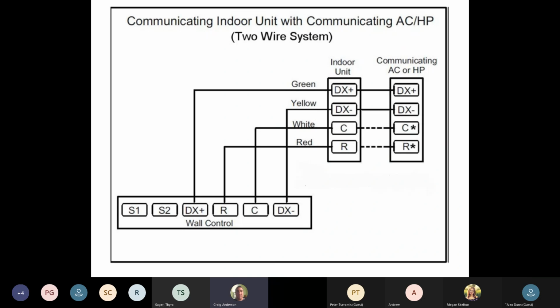So here's the wiring diagram for our communicating units. So we have a communicating stat via a communicating indoor unit, whether it's a furnace or an air handler, 4 wires. Outdoor communicating unit, 4 wires as well. Always run 4 wires to the stat to the outdoor unit. Some outdoor units don't need a 4-wire to communicate. Run it for the price difference between a 3-wire and a 4-wire. Run the 4-wire. You might not need the 1 wire. So 4 wires indoor, 4 wires outdoor.